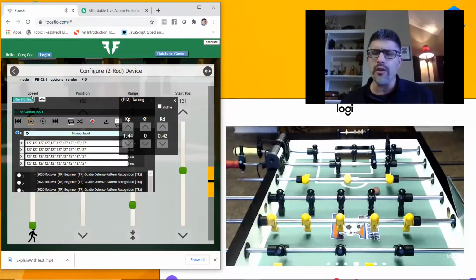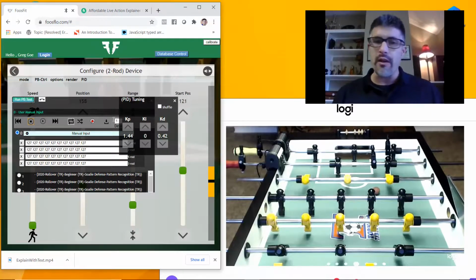That's really all I want to talk about with the PID. Just remember, playback mode is the one you'll probably have to adjust the most, if ever, and it's just the KP: up moves it away from the device, down moves it towards it. If you notice weird things going on, the rods shifted a little bit, hit the calibrate button, then go on with your practicing and everything will be fine. So that's PID and calibration.